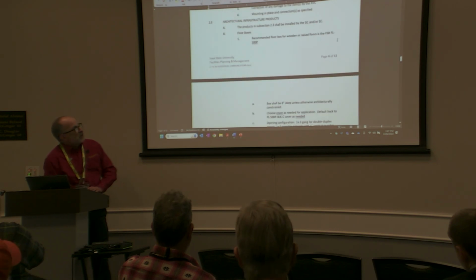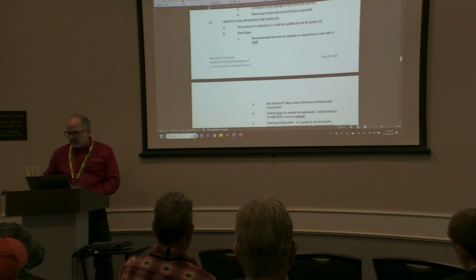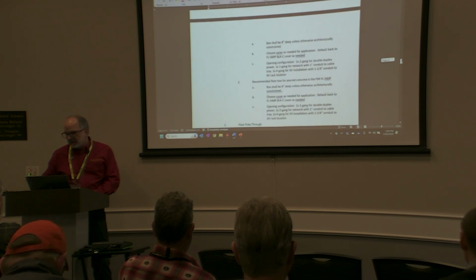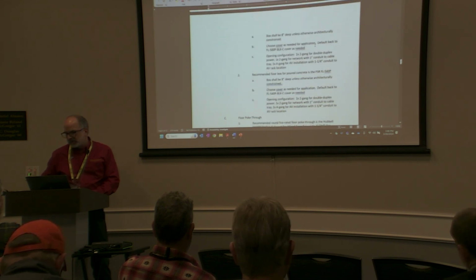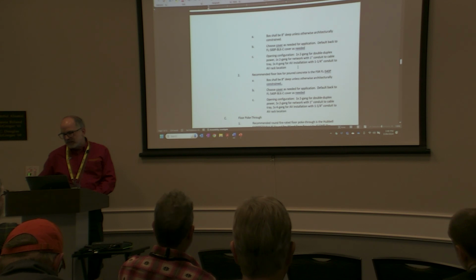So your floor boxes will be this. For wooden or raised floors, you're going to use an FSR FL 500P, and it's going to be 8 inches deep unless otherwise architecturally constrained. You'll choose a cover as needed for the application, default to this cover, and inside the box you'll have one 2-gang for double duplex power, one 2-gang for network with 1-inch conduit to the cable tray, one 4-gang for AV installation with 1.25-inch conduit to the AV rack location. And then we do it all again for poured concrete.